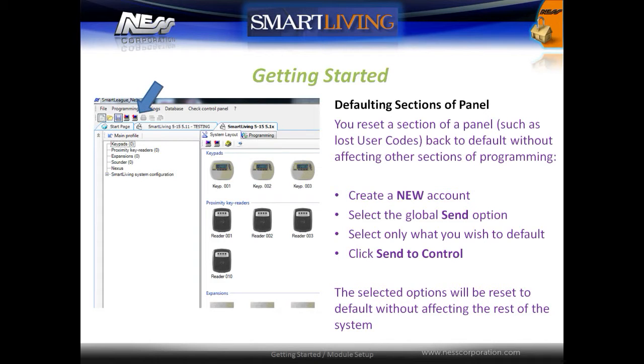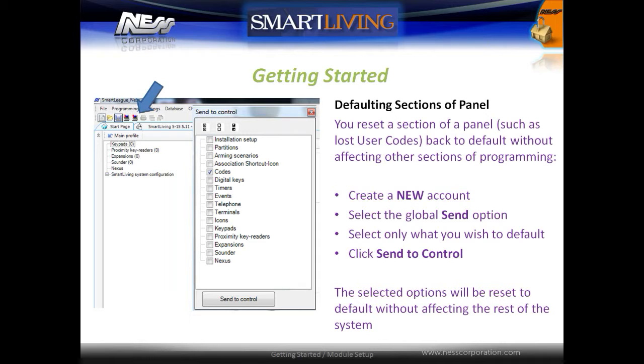It is possible to reset sections of the panel using the software, such as lost user codes, back to their factory default without affecting other sections of the panel. Create a new account, select the Global Send option, and then select only what you wish to default. Click Send to Control. The selected options will be reset to the default values without affecting the rest of the system.